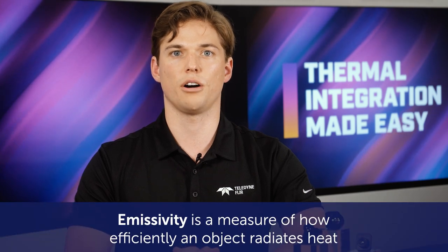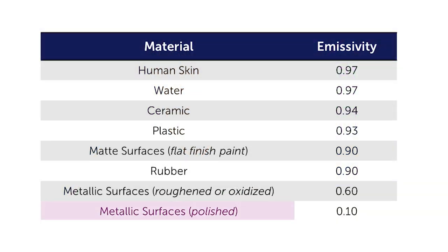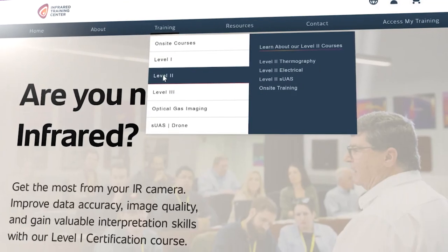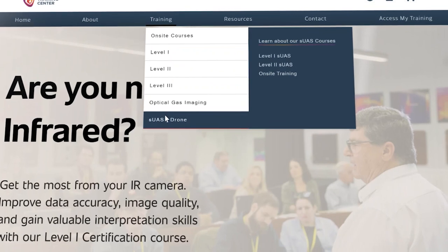Radiometric accuracy is affected by the characteristics of objects being measured, the environment, and the camera. Emissivity is a measure of how efficiently an object radiates heat. Highly polished metallic surfaces will have a lower emissivity of about 0.10, matte surfaces are around 0.90, while human skin and water are about 0.97. Objects must have a high emissivity to be measured properly, so make sure your test targets have a high emissivity value. You can learn more about emissivity at our website and through training with the Infrared Training Center at infraredtraining.com.